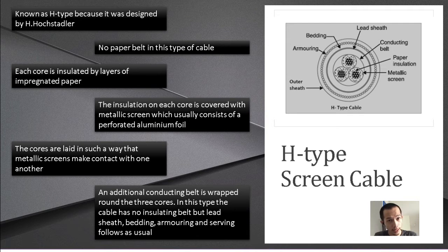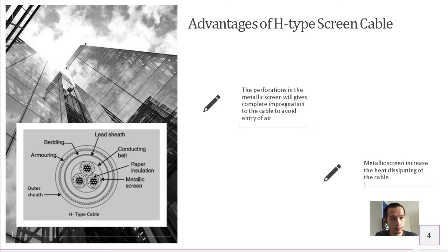And also an additional conducting belt is wrapped around the three cores. In this type, the cable has no insulating belt, but lead sheath, bedding, armoring, and serving follows as usual. So, with the build structure of the H-type cable, it provides advantages where the perforation in the metallic screens will give complete impregnation to the cable to avoid the entry of air. Meanwhile, the metallic screens covering the cores will also increase the heat dissipation of the cable itself.